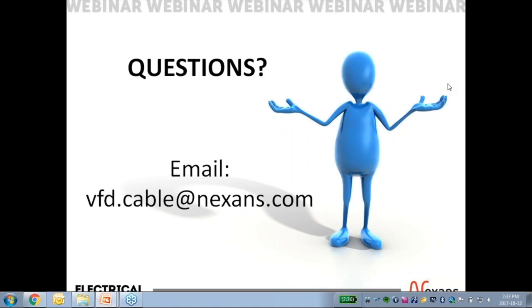Very good. Now this one, we have Ted, and he's saying, I have frequently specified an inductor near the motor. Does the use of variable frequency drive cable eliminate this need? I don't think it would. I think what you're doing there, if I'm not mistaken, is trying to help with this reflected wave phenomenon. This is where it may be important to get a hold of the drive manufacturer and get some information on how much of an effect adding that reactor to the drive system would help. There may be instances I could imagine where it may not help. The drive manufacturer is important here to consider.